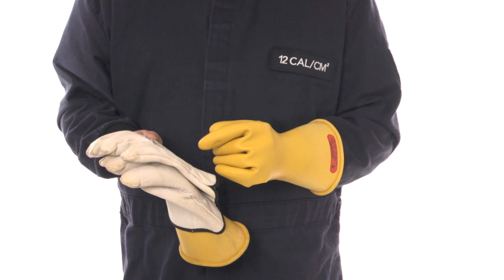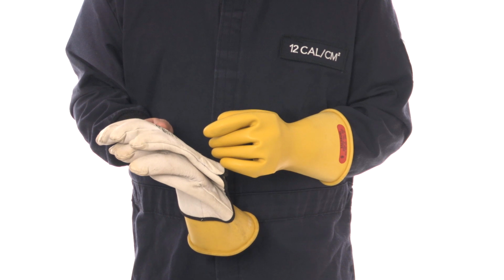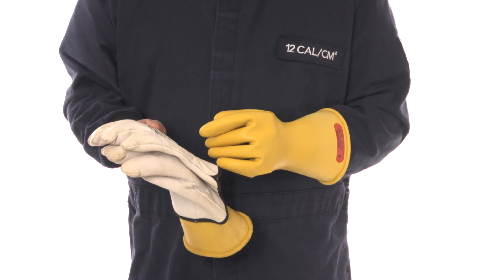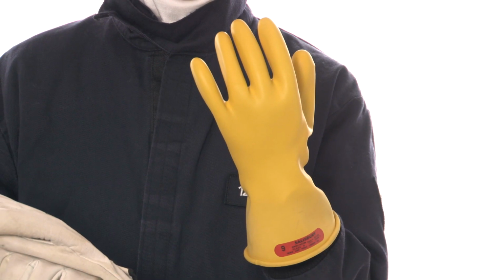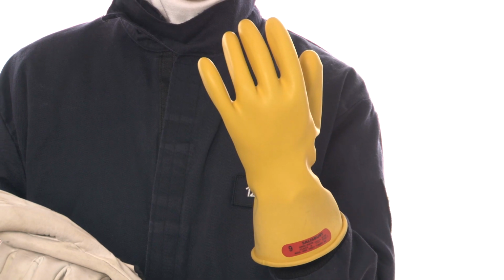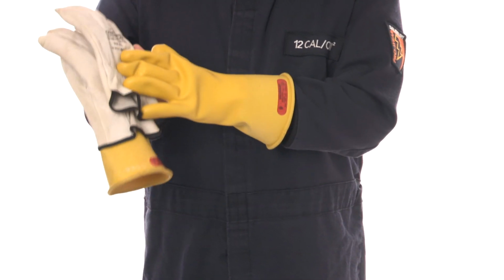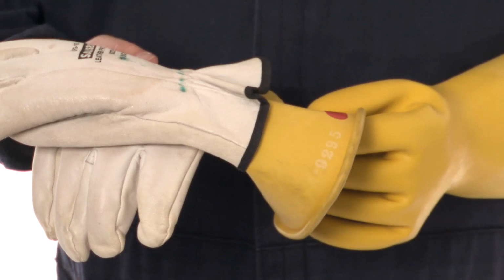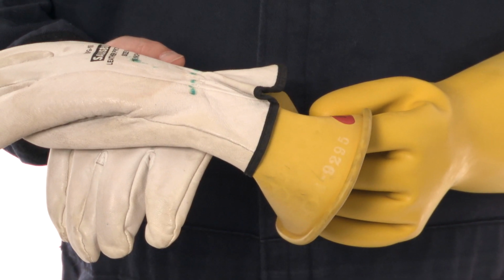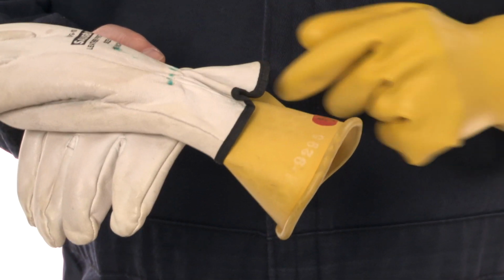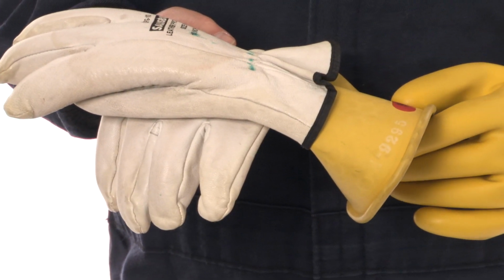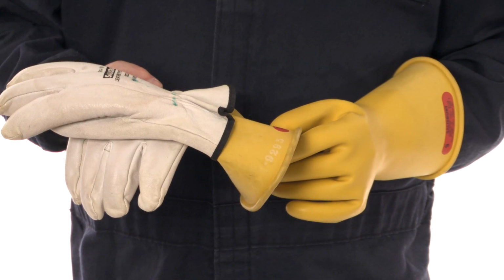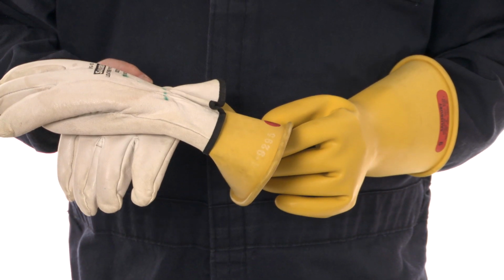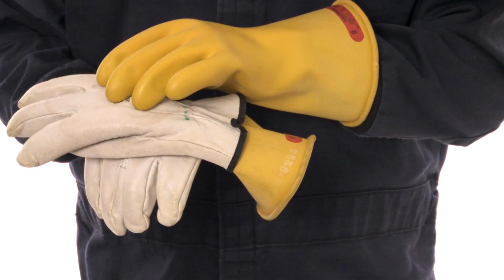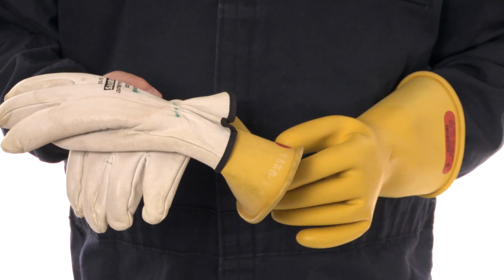It is important to note with the rubber insulating gloves with leather protectors, never to just wear the inner glove, the dielectric portion of the glove. They must be worn with the outer leather protector. Also note that there is a minimum cuff distance between the outer leather protector and the inner dielectric portion of the glove. This is a must. There has to be this cuff distance between the outer leather protector and the inner dielectric glove.